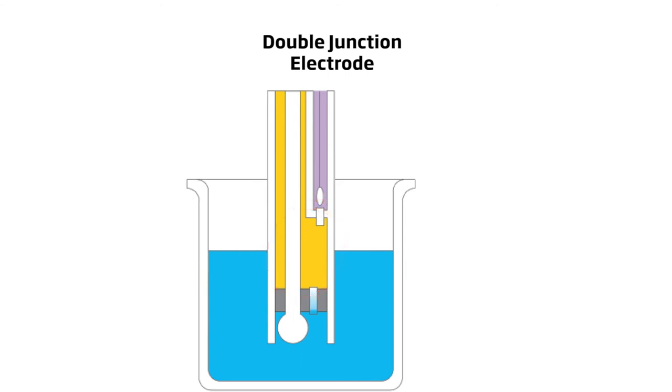The absence of silver chloride prevents the issues associated with single junction electrodes from occurring.